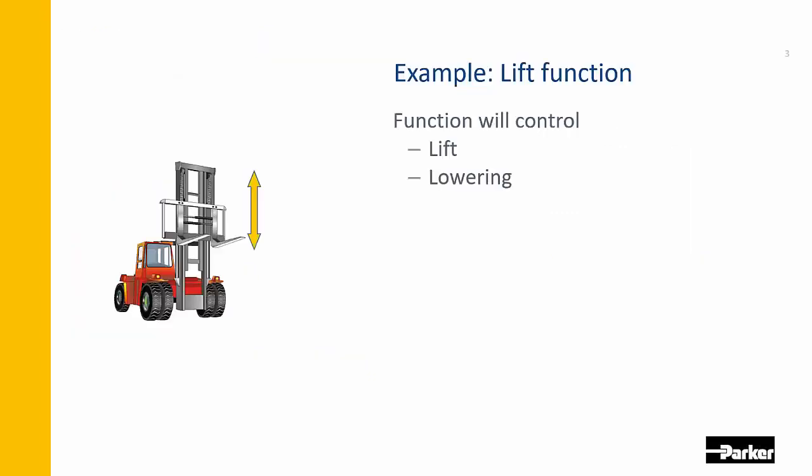So the function is a familiar one: lift truck with proportional lift and lowering. The functional safety aspect of this is that we see this as a hold-to-run function. When the operator lets go of the lever, the movement needs to stop, and it's not supposed to be restarting under any other conditions other than the operator actively lifting or lowering.